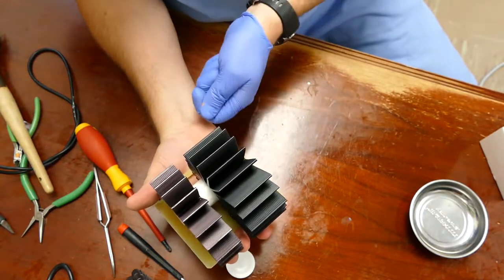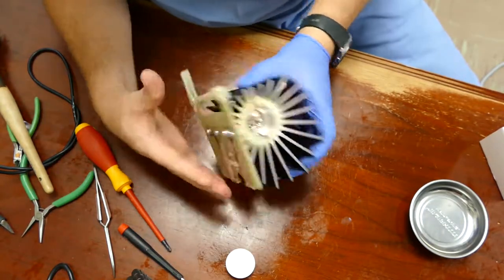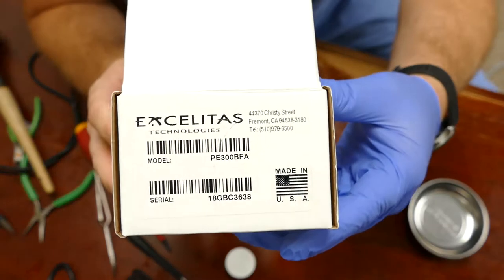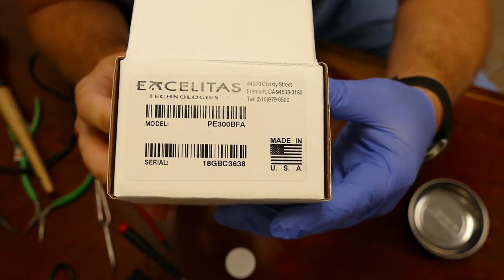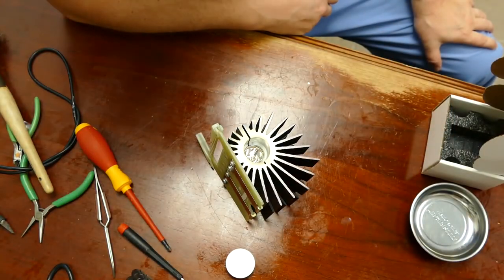So when they go to install it, they see the flag, they pull the tape off and pop the bulb in. You're good to go. But that's how you rebuild the Karl Storz xenon bulb, 300 watt. The part number is right there: Excelitas PE300BFA. Thanks for watching guys, I hope you enjoyed this video.